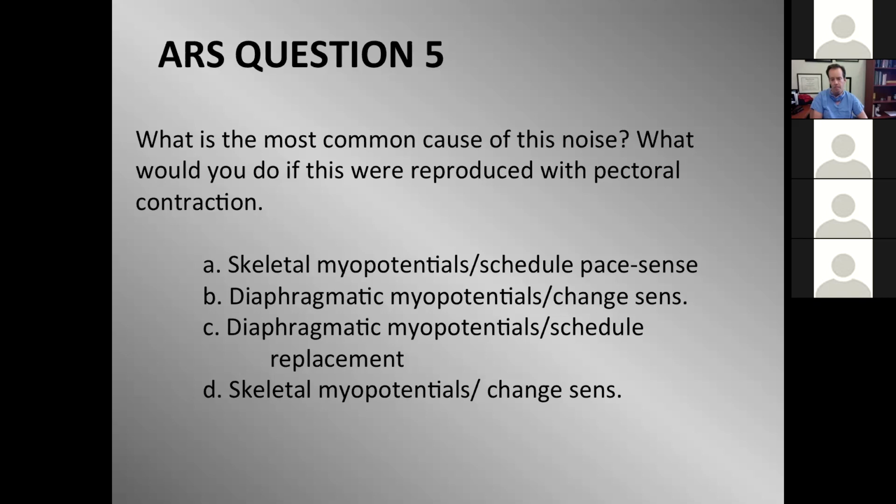Let's say the site of the fracture is located in such a way that if you reprogram them from dedicated to integrated bipolar and the noise goes away, can you leave them programmed that way? You can. But that's a specific situation, you would have to have a ring electrode fracture that's isolated. And if you had the luxury of being able to exclude that pace sense ring and change it over to an integrated bipole, that's a theoretical fix. You could program around that.